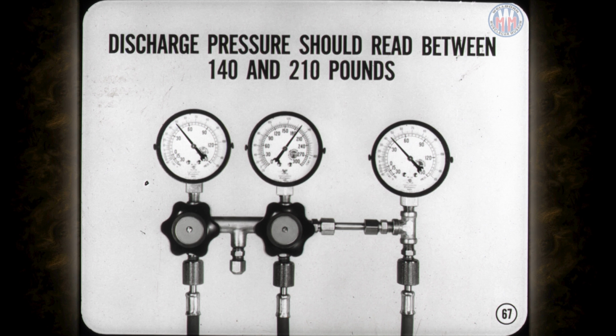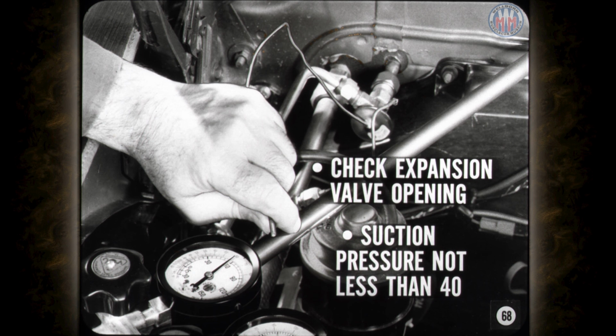Discharge pressure should read between 140 and 210. Discharge pressure lower than 140 indicates that the EPR valve does not open properly, that the expansion valve is closed, or that compressor capacity is low. To find the cause of low discharge pressure, you first check the expansion valve for proper opening by warming its thermal bulb in your hand. With the expansion valve open, the suction pressure reading should not be less than 40. Low pressure here points to a faulty expansion valve.